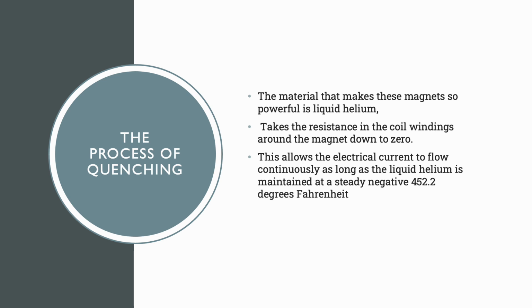In the next few slides, we are going to look at the events preceding a magnet quench. As we all know, the material that makes these magnets so powerful is liquid helium, which takes the resistance in the coil windings around the magnet down to zero. This allows the electrical current to flow continuously as long as, and this is key, the liquid helium is maintained at a steady negative 452.2 degrees Fahrenheit.